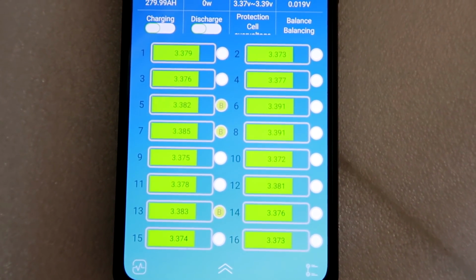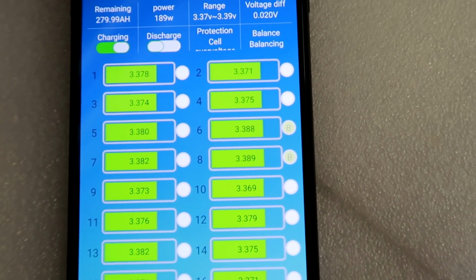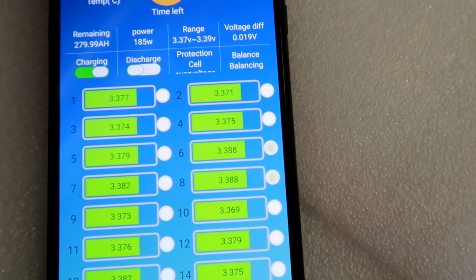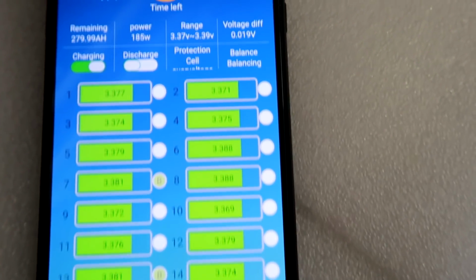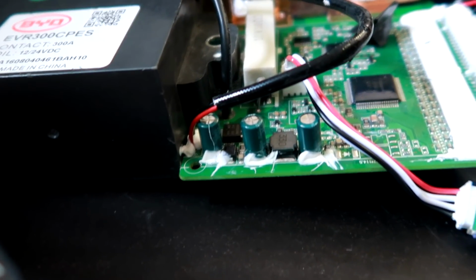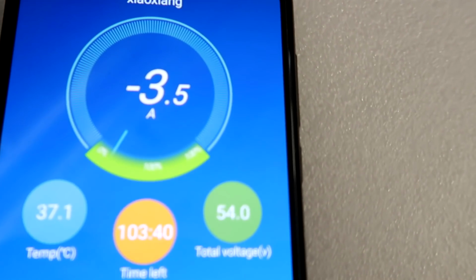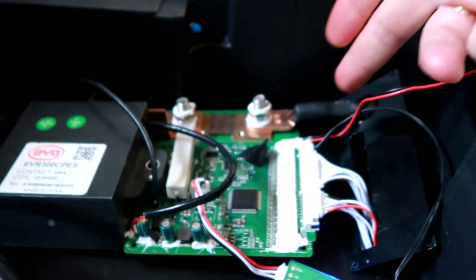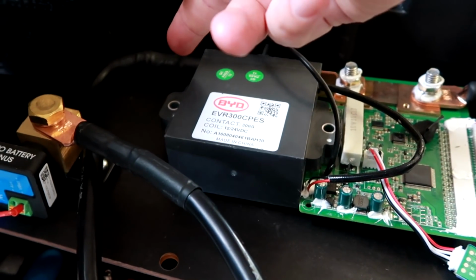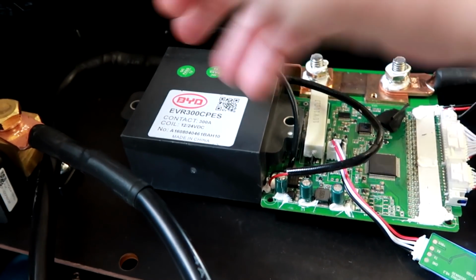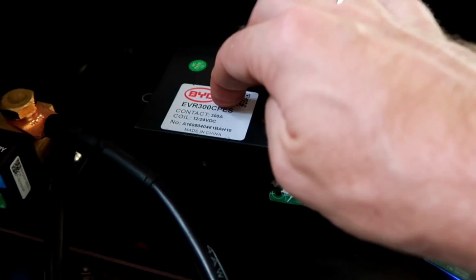Alright, so battery's voltage is going down. Okay, just put some load on the inverter to discharge the batteries quicker. But you can see the relay is still off, and we are discharging with 3.5 amps. So how is the amp going from here to here, or the other way around, doesn't matter, if the relay is off? That is not right.